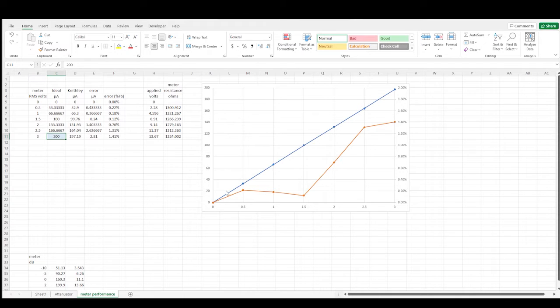To look more closely at the data, though, I first need to make an assumption for the full-scale reading at 200 microamps. This meter does read slightly above the 3-volt mark, but nevertheless, I'll make the assumption that 200 microamps corresponds to the 3-volt mark. So, based on that assumption, I'm able to calculate the error as a percentage of full-scale, and here's what that looks like, represented by the orange line.